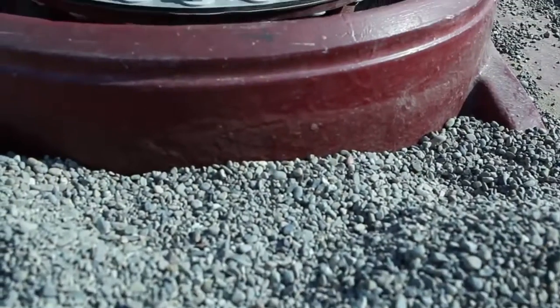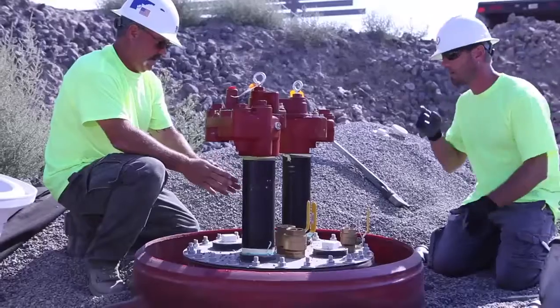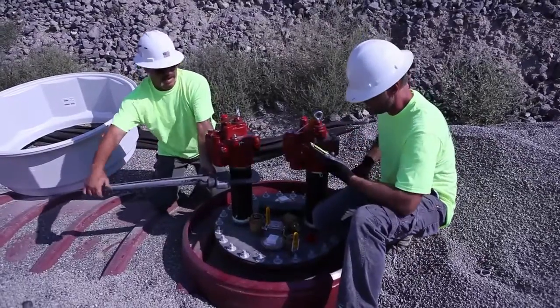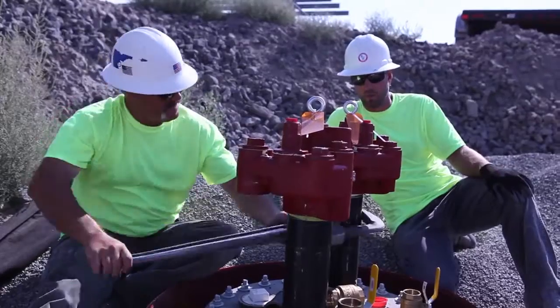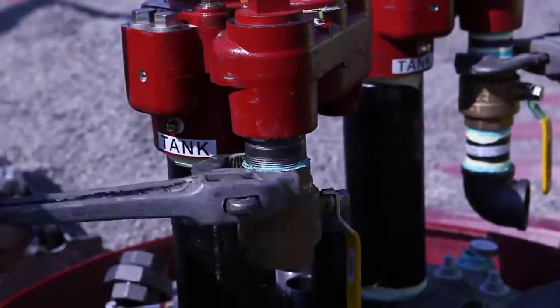In this install we're actually manifolding two-horsepower pumps together to make sure that that capacity is there. When you install two STPs into one sump you do have a little bit of spacing to work through, but all you need to do is put ball valves on the discharge of each so that you can isolate one to work on it while the other is up and running — so you never have to shut your site down.